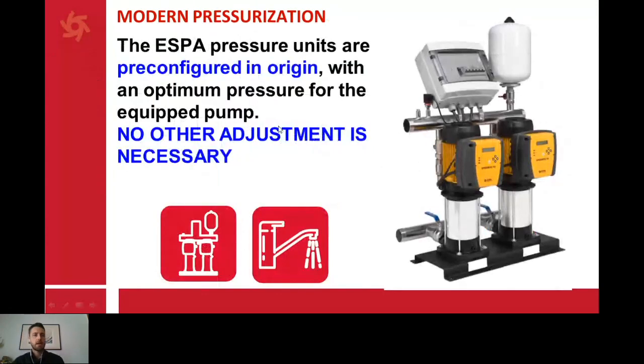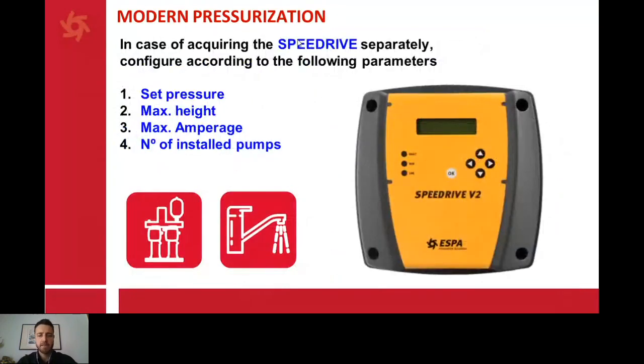The ESPA pressure units are pre-configured from the factory, so you don't need to set anything else. Just in case you want more or less pressure, you can easily adjust it, but no other adjustment is required. In case of acquiring a speed drive separately, you just have to set the pressure, the maximum height, the maximum amperage, and the number of installed pumps, because it's important that the speed drive detects how many pumps are installed to communicate correctly with them.